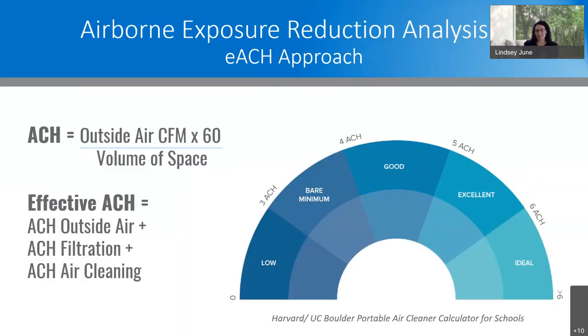The most predominant method used in the studies was calculating the effective air changes per hour, or EACH, as a proxy for IAQ. Where air changes per hour, the ACH, is the rate of the total volume of air in a space being replaced with fresh or clean air, EACH is the quantification of the effectiveness of various air cleaning strategies, so some combination of dilution, ventilation, filtration, and UVGI. EACH is calculated by adding the ACH of the individual strategies, and then the EACH can be compared to or stacked with strategies to meet a desired EACH target.